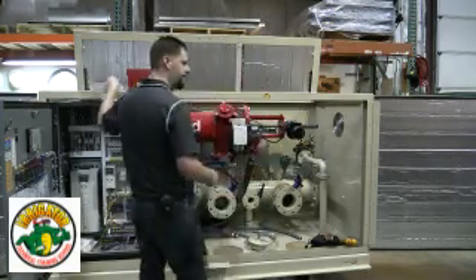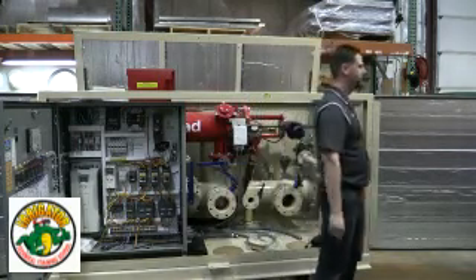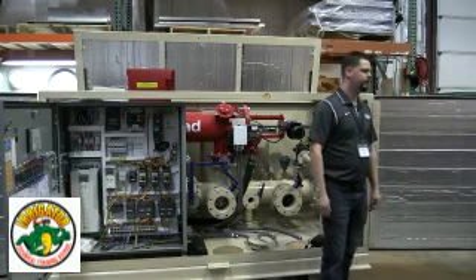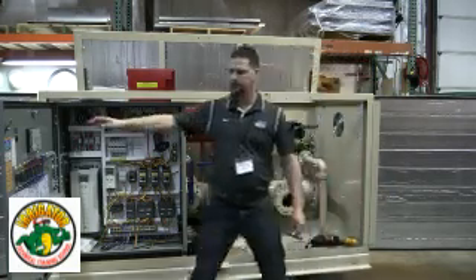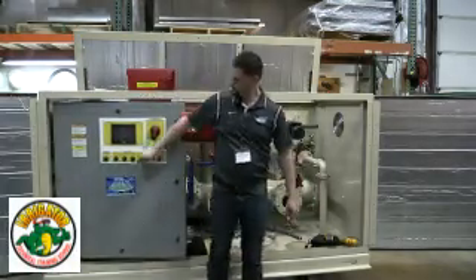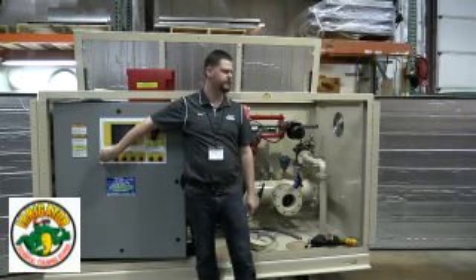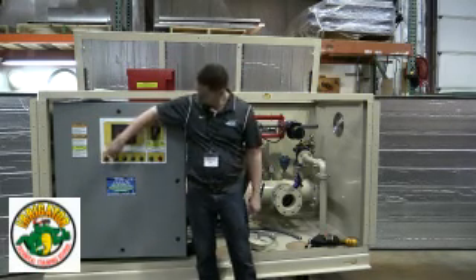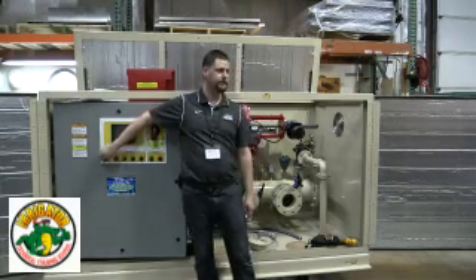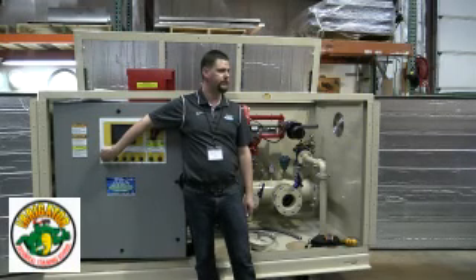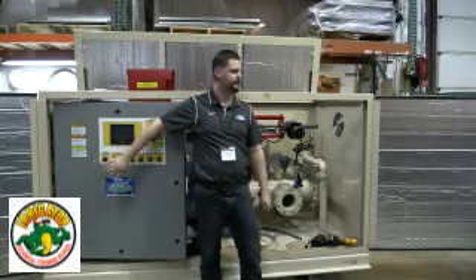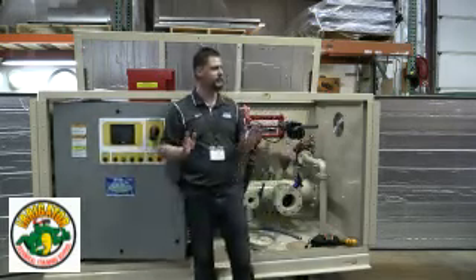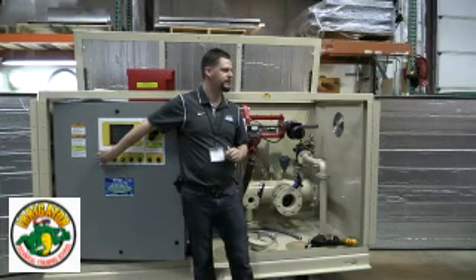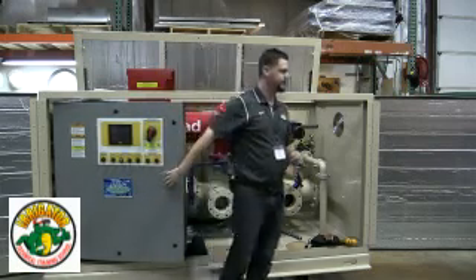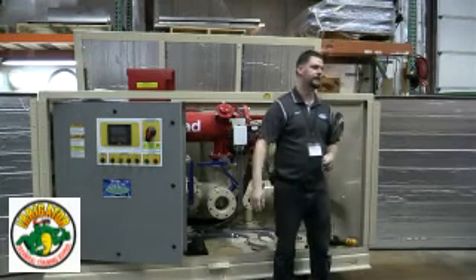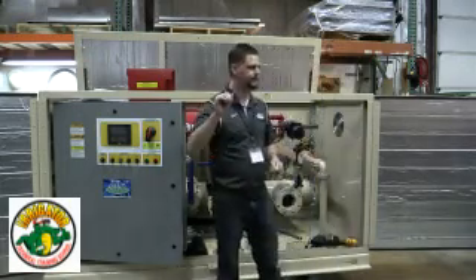So, here we are again at a pump station with a pipe full of air. While we're going through testing some of these other things, let's get some of this air out of the pipe. Turn the speed pot all the way down because we're slowly filling up the pipe. We're not blasting it. Pick out your smallest pump, put it in hand, slowly dial it up. If you don't see pressure right away and you're already at the halfway point, I'll just leave it there for 5 minutes while I'm doing something else. I'll come back. Oh boy, there's a little bit of pressure. Once I see a little bit of pressure, I'll kick it up a notch just to make sure it's not going to skyrocket. And then as soon as we get to 5 to 10 pounds, depending on the system and your familiarity with it, I'll just turn the pump off.